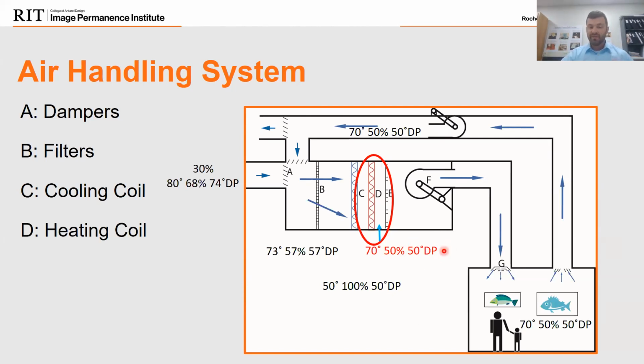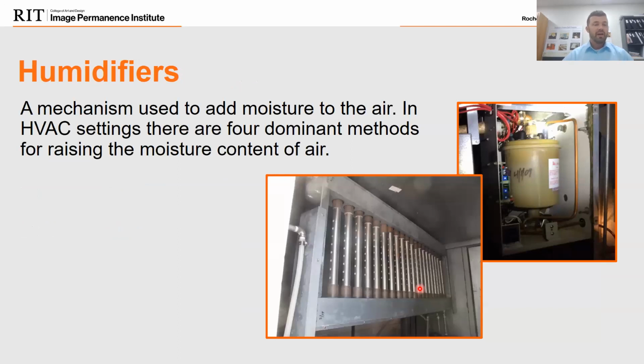We're at 70 degrees, 50%. So we now have the condition we want for the room, but we have two more stops, if you will, within the unit. We have to cross E, which is our next component, and then out of F. Well, E is going to be on our unit, the humidifier.